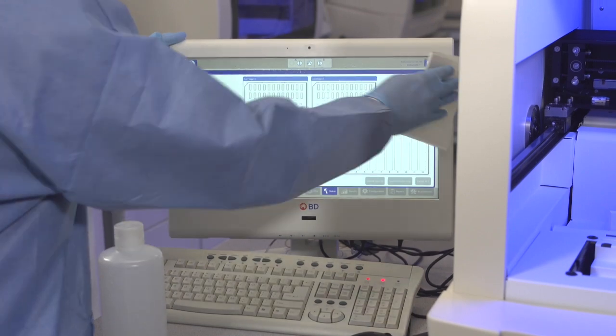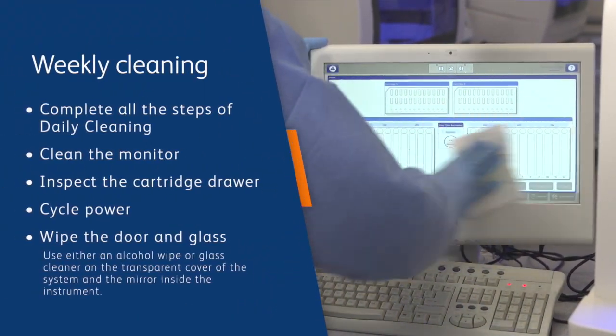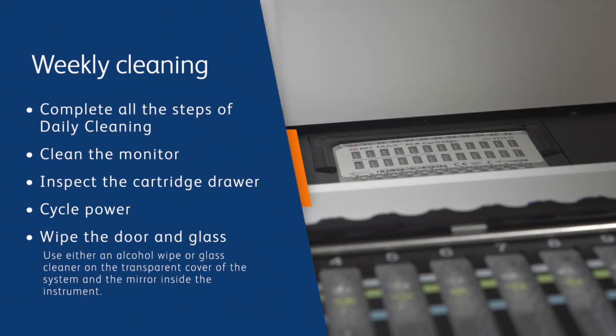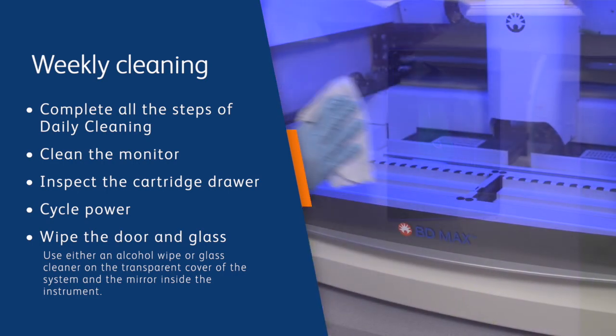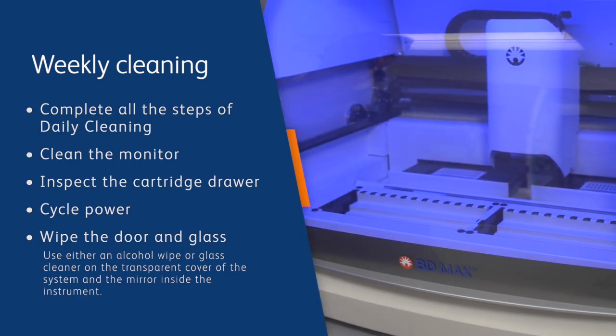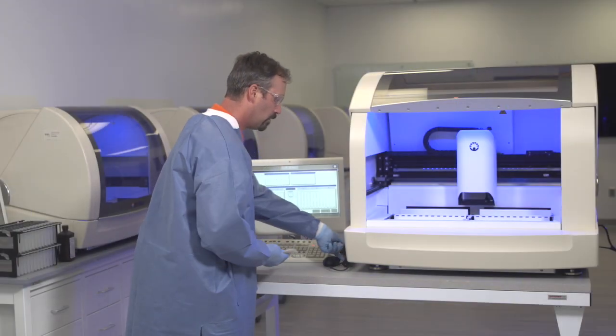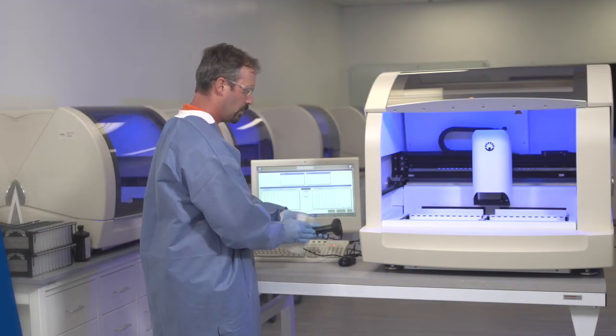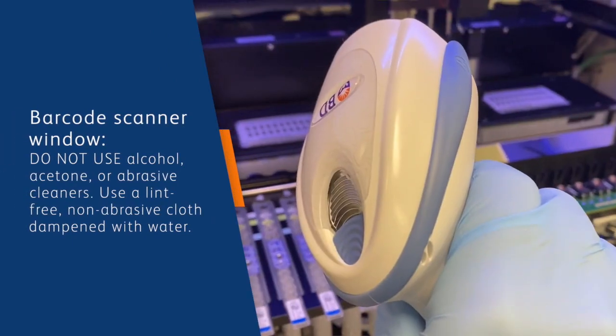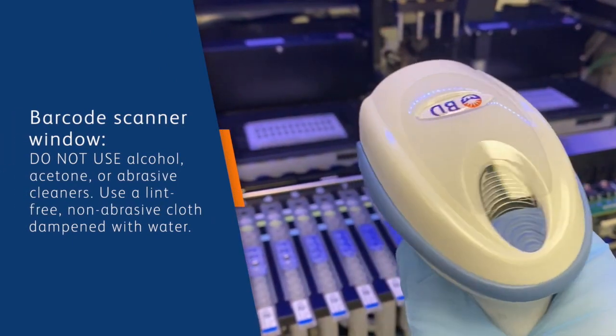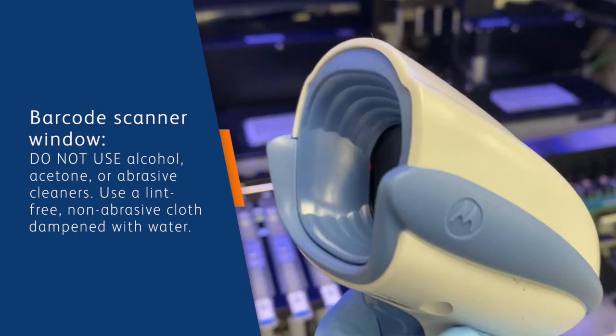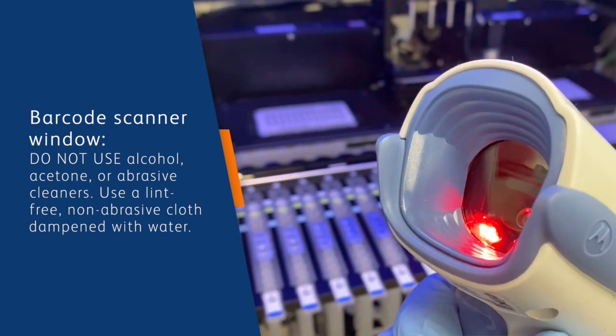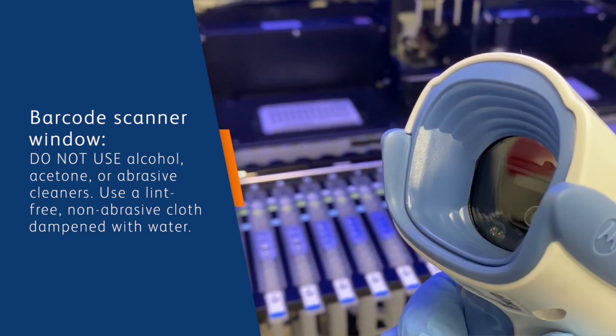Weekly maintenance includes all of the steps of daily cleaning, with the addition of cleaning the monitor, inspecting the cartridge drawer, and cycling power. Use proper personal protective equipment, and follow safety guidelines. The handheld barcode scanner has a clear window through which the scanner beam passes. If the scanner is giving read errors when attempting to scan, you can try cleaning the scanner window. To clean the window, use a lint-free non-abrasive cloth dampened with water.